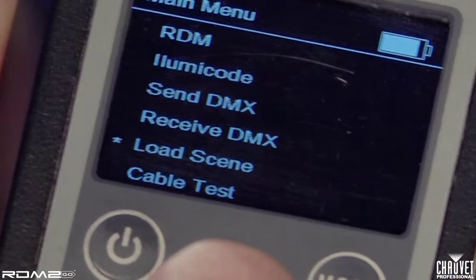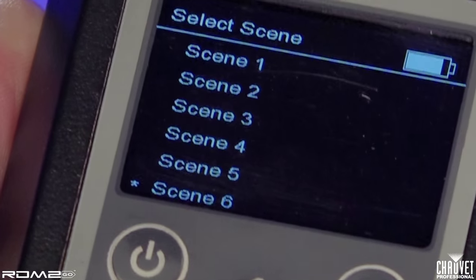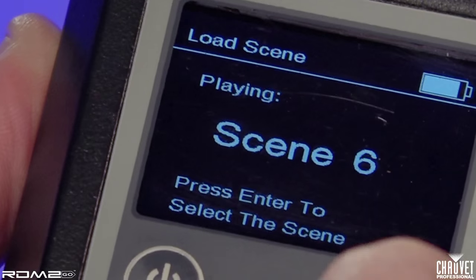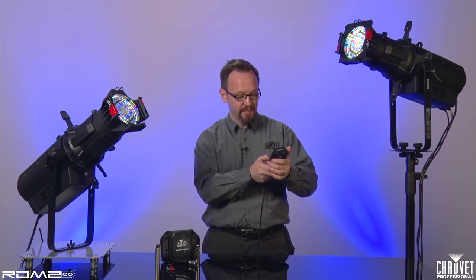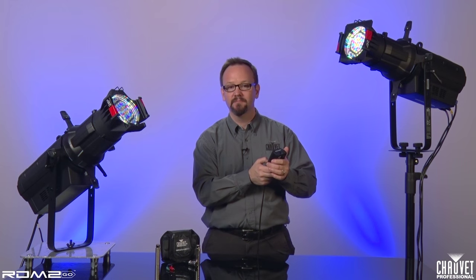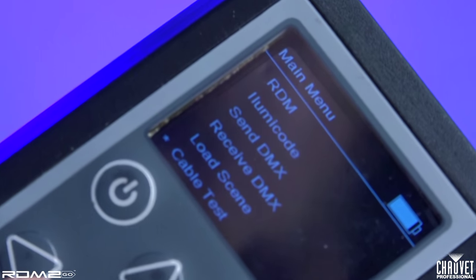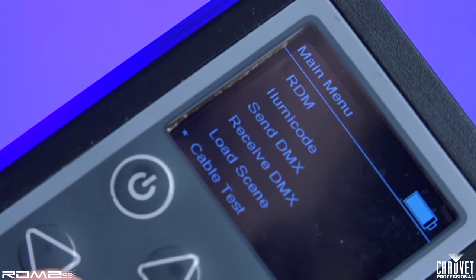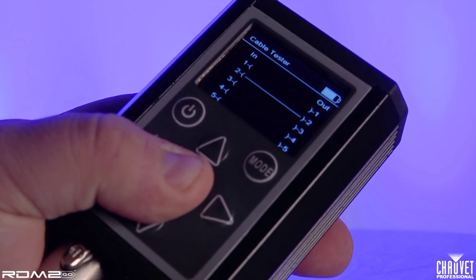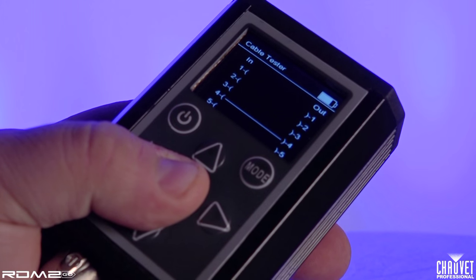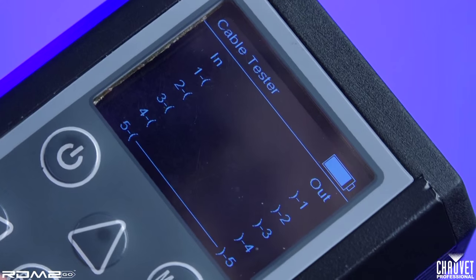Next, you can see that I can load any scene that I have programmed previously. One other great feature of the RDM2GO is that it can act as a cable tester. If I plug in a DMX cable, it will tell me which pins are connected and which are not working. A straight line across indicates a good connection; anything else indicates a fault.